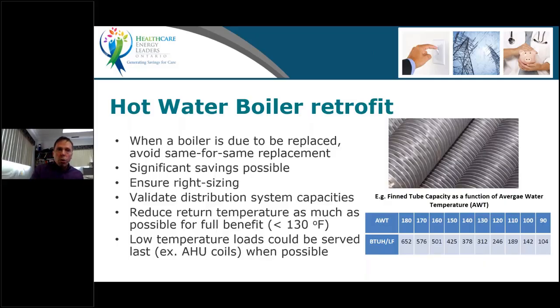When you do a hot water boiler retrofit, be careful not to go for a same-for-same replacement. That's the last thing you really want to do. It's sometimes a once-in-a-lifetime opportunity, because boilers can last a long time if they're well maintained. So when you replace, look at your possibilities. If you have a 20 MBH boiler, don't just put a 20 MBH boiler back. Make sure you right size.